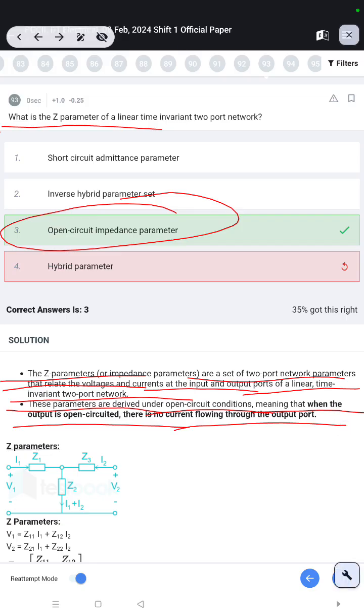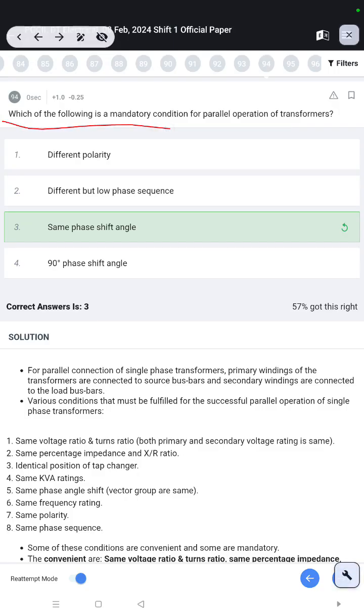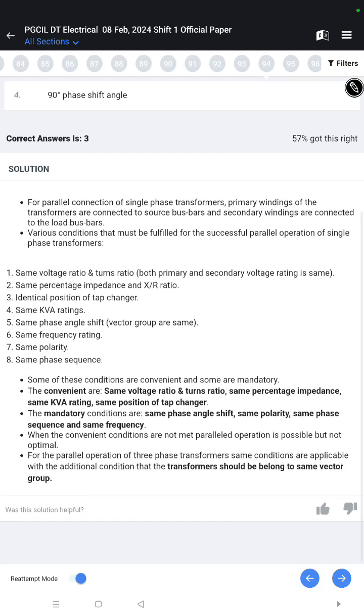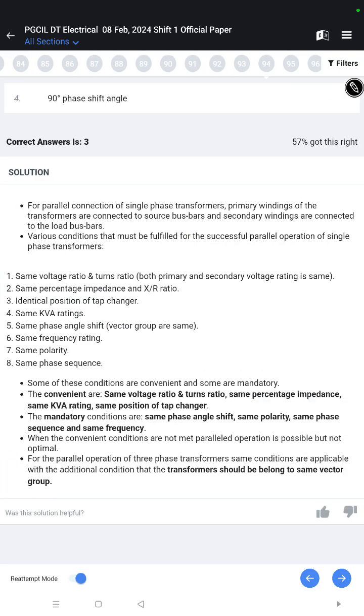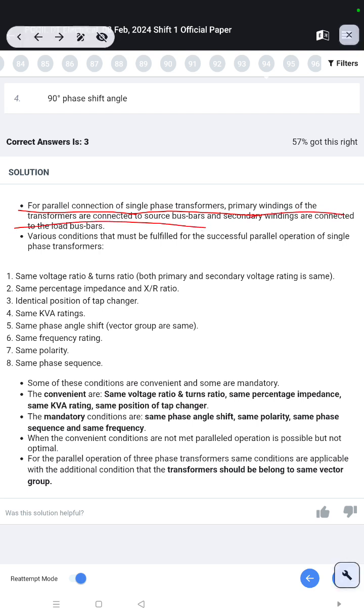Which of the following is a mandatory condition for parallel operation of transformers? Same phase shift angle. For parallel connection of single phase transformers, the primary windings of the transformers are connected to the source bus bars and the secondary windings are connected to the load bus bars. Various conditions must be fulfilled for the successful parallel operation of single phase transformers.